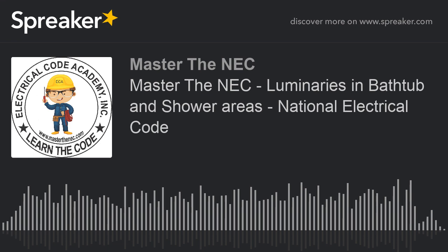So it doesn't mean you can't have them in these spaces. You just have to be aware of what you put in there. I routinely see on Instagram and places like that, believe it or not, people with suspended ceiling fans in that 3 foot by 8 foot zone. They think it's outside of the shower, so it's okay, but you see in (D)(1) that it's prohibited. So you have to stop, look at it, and think about what you're putting in there. Sometimes the owners want some weird stuff when they're picking out their luminaires for their dwelling, and you have to rein them in a little bit and say, no, you can't do that. We can't have that in there.